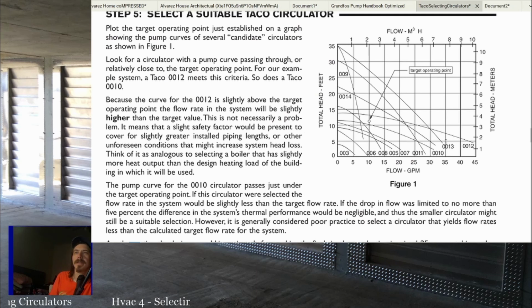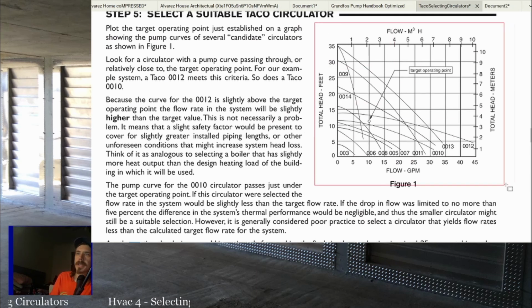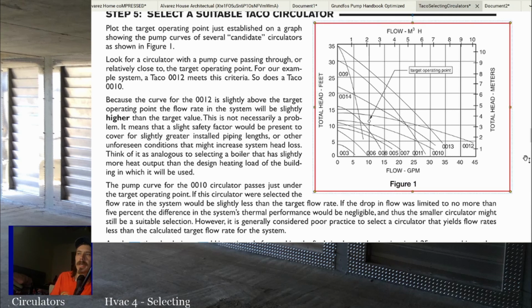So this graph is kind of neat. This is obviously all Taco pumps, right? You can use any pump manufacturer's curve though. These are all just different pump curves. So what they're showing on this chart, if you're familiar with Taco circulators, then you can probably recognize these numbers. They have a 007 pump. That's a pretty common pump. A 009, but they got a bunch of them. You got 0012. All right. 0013, 0010, 003, 006, 008. 008's pretty common too. So these are all your different pump types.